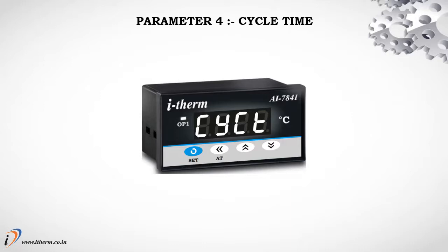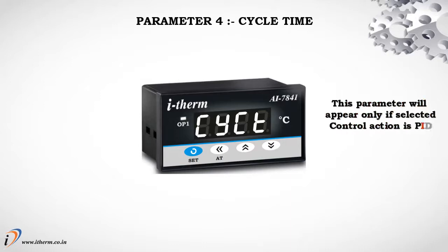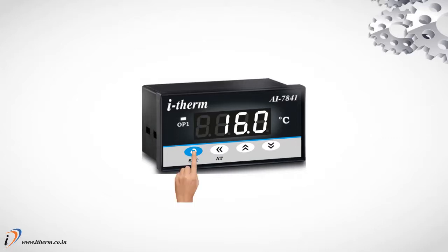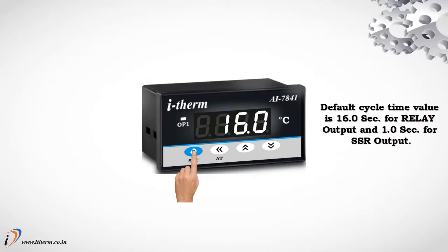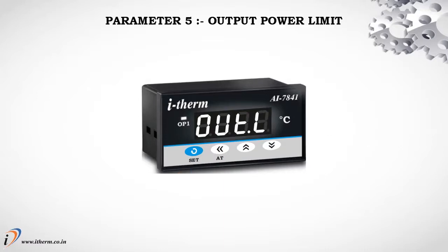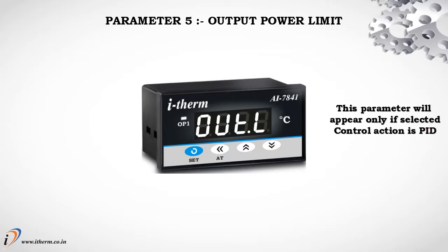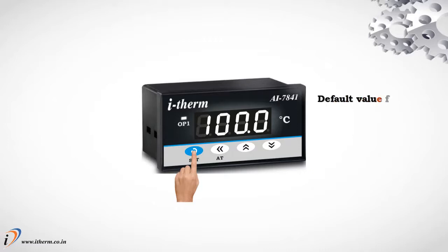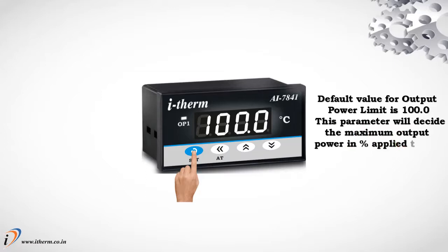Parameter 4, cycle time. This parameter will appear only if selected control action is PID. Default cycle time value is 16.0 second for relay output and 1.0 second for SSR output. Parameter 5, output power limit. This parameter will appear only if selected control action is PID. Default value for output power limit is 100.0. This parameter will decide the maximum output power in % applied to the load.